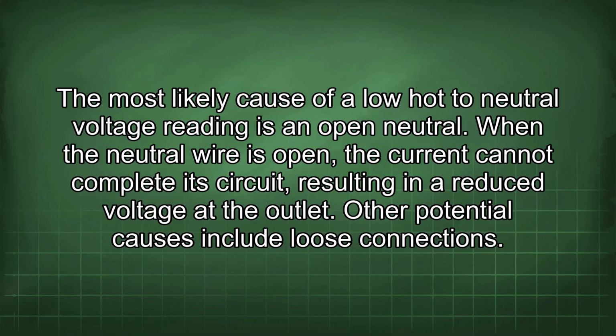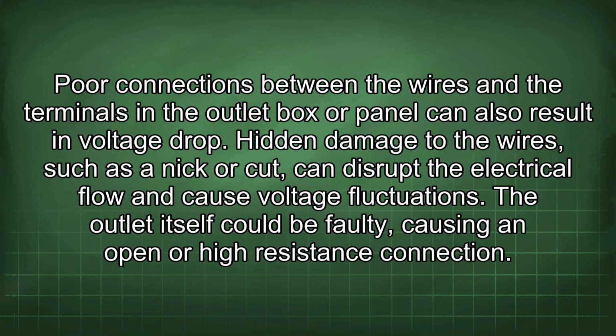The most likely cause of a low hot to neutral voltage reading is an open neutral. When the neutral wire is open, the current cannot complete its circuit, resulting in a reduced voltage at the outlet. Other potential causes include loose connections. Poor connections between the wires and the terminals in the outlet box or panel can also result in voltage drop.